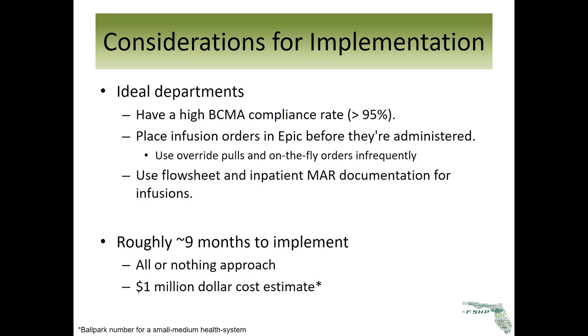Secondly, orders need to be placed in Epic before they're administered. That's because the order has to translate from Epic over to the pump. If they put it in on the fly or in an emergency situation, the order may not transmit in time for the medication to be administered. Finally, they need to utilize some kind of documentation like flow sheets or the inpatient MAR. This will allow the pump to transmit the data back to the EHR and allow it to store and document it there.